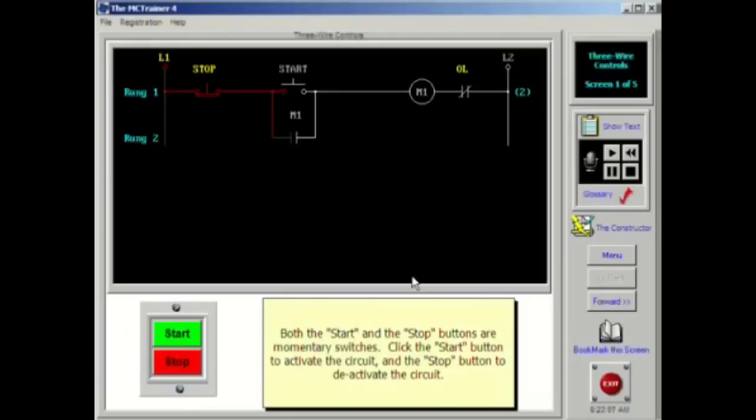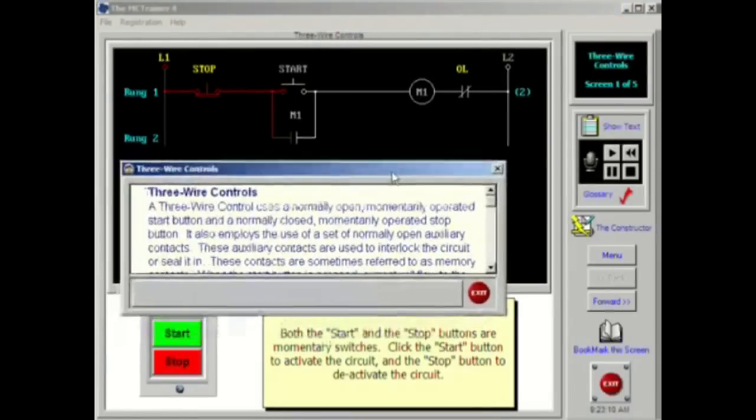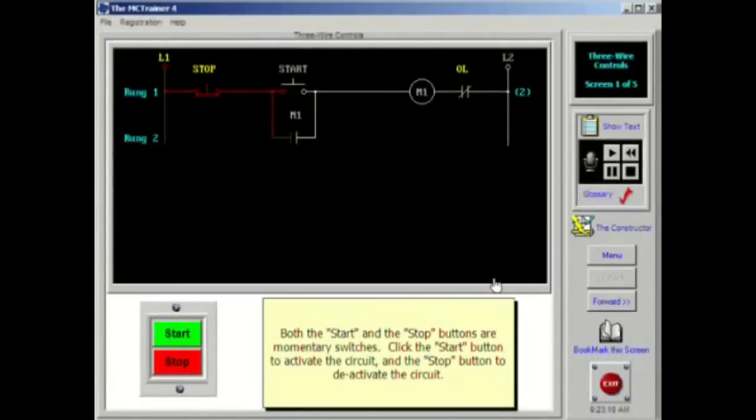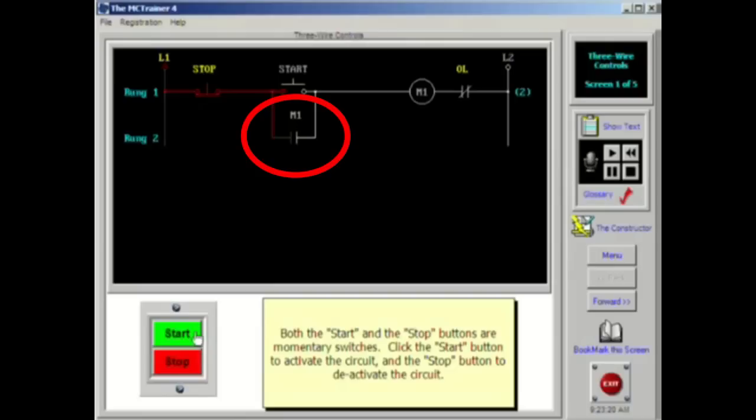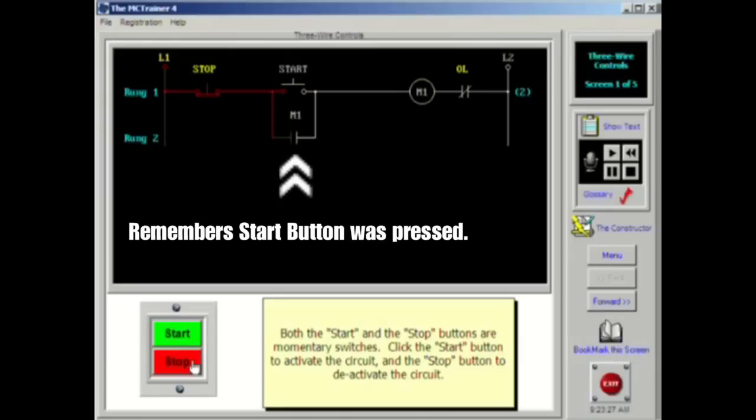A three-wire control uses a normally open, momentarily operated start button, and a normally closed momentarily operated stop button. It also employs the use of a set of normally open auxiliary contacts. These auxiliary contacts are used to interlock the circuit or seal it in. These contacts are sometimes referred to as memory contacts.